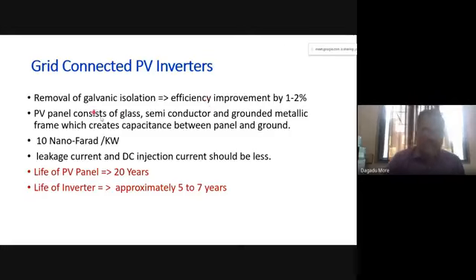Now we see the construction of a PV panel. A PV panel consists of semiconductor, glass, then a grounded metallic frame. And this rests on the ground, which creates a capacitance between panel and ground. So this will be one capacitance that will always be associated with the PV panel. That capacitance is the panel to ground capacitance, and this value will be just 10 nanofarad per kilowatt rating of the panel.